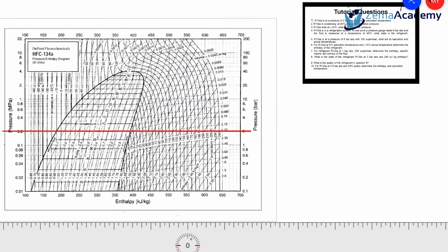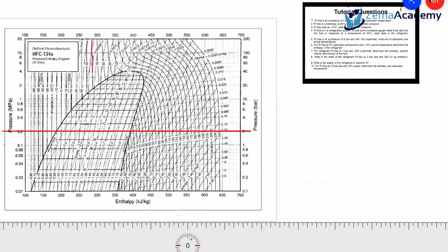Previously, last week when we covered the P-h chart, we looked at the temperature pattern. For instance, if I follow 60 here, and follow the line straight horizontally, it's still 60, and if you come out and follow the line, it's still at 60. Every temperature works that way, and each suction pressure will have a dedicated suction temperature. So by looking at the suction pressure, you can automatically read the suction temperature which relates to that.